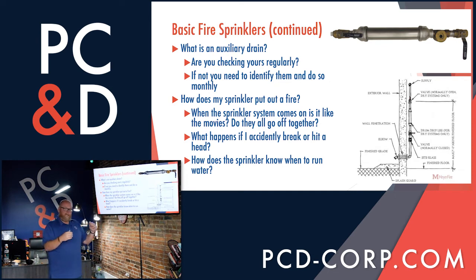So we've talked about pumping air in. We talked briefly about one of the things that's missed often, which is draining the water off of your air compressors. So that air, as it's being pumped into your dry system, it's got some moisture in it. When it gets into your riser system and up into your sprinkler system, that moisture will start to turn to water. As the temperature fluctuates, goes up and down, you'll also have some humidity in that air that's being pumped in start to turn to water. Remember, what's the point of having a dry system? It's because it's in a cold area and we don't want that pipe to freeze.